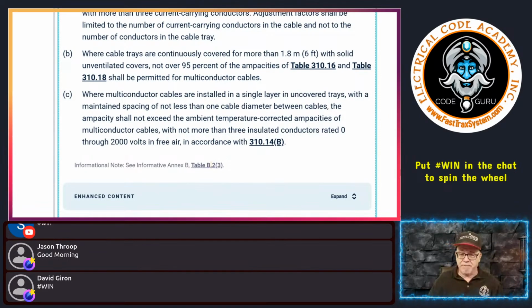If we do all that, it says the ampacity shall not exceed the ambient temperature corrected ampacities, which means that you still may have to do an ampacity based on ambient temperature, but you get to ignore any of the requirements under 310.15(C)(1).